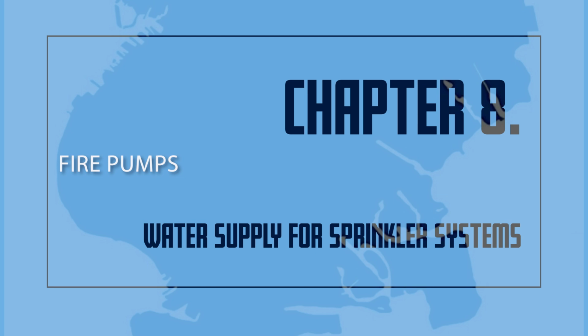Automatic fire pumps must have their suction under a positive head to avoid the delays of drawing water from a supply source. Under positive head simply means that the water supplying the pump must be fed into the fire pump under pressure. This can be achieved by connecting the fire pump to a suction tank. Water is forced into the pump because of gravity.